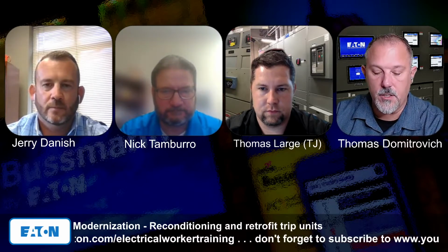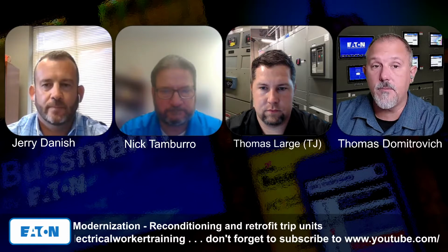The use of reconditioned circuit breakers shall comply with 1 through 3, and this is where it tells us that you cannot recondition a molded case circuit breaker, but you can recondition low voltage and medium voltage power circuit breakers. And you can also recondition high voltage circuit breakers. That's because that circuit breaker behind TJ's head is, I call it, the Swiss watch of breakers, because you can do a lot to those things, right?